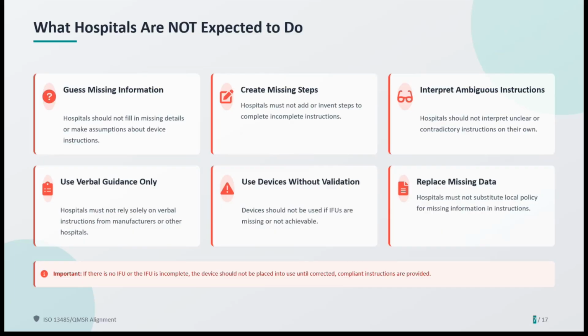Let's put this into the context of a non-compliant process, and I want to tie it to a real example. In one case, we identified a missing dry time for a device in the IFU, which is an automatic stop on reprocessing for our client. The referring department wanted the reprocessing done, so they called another hospital and asked, "What dry time do you use?" And that hospital said, "Well, we dry for 15 minutes." This is a great example of a non-compliant process. Calling another facility is not following the IFU and does not meet regulatory expectations.